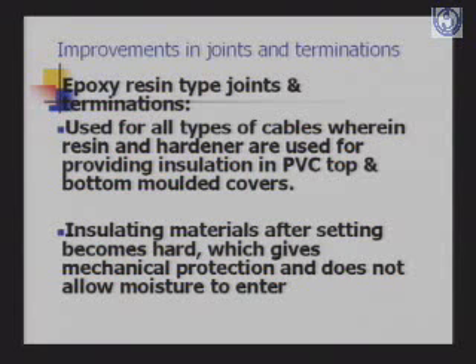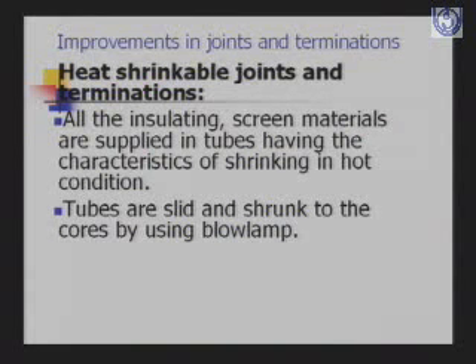Other improvements in joints and terminations are the epoxy resin type joints and terminations. This is used for all types of cables wherein resin and hardener are used for providing insulation in PVC top and bottom molded covers. Insulating materials after setting become hard, which gives mechanical protection and does not allow moisture to enter the cable. Then there are the heat shrinkable joints and terminations. All the insulating screen materials are supplied in tubes having the characteristics of shrinking in hot condition. Tubes are slid and shrunk to the cores by using a blow lamp.